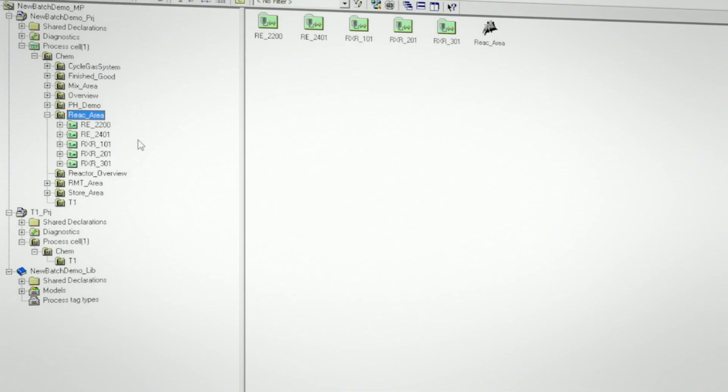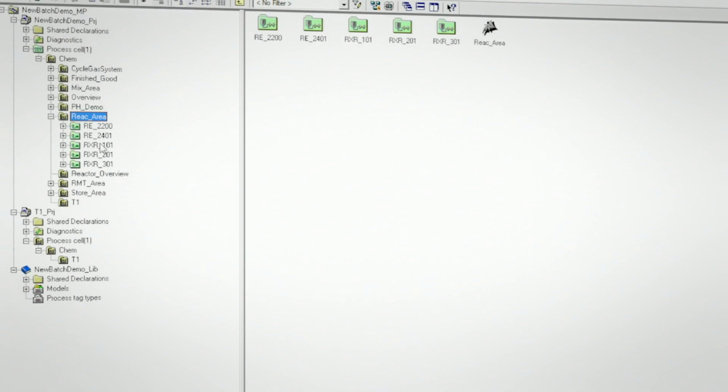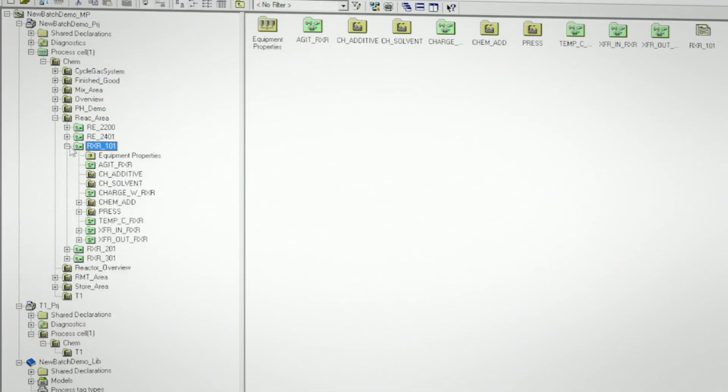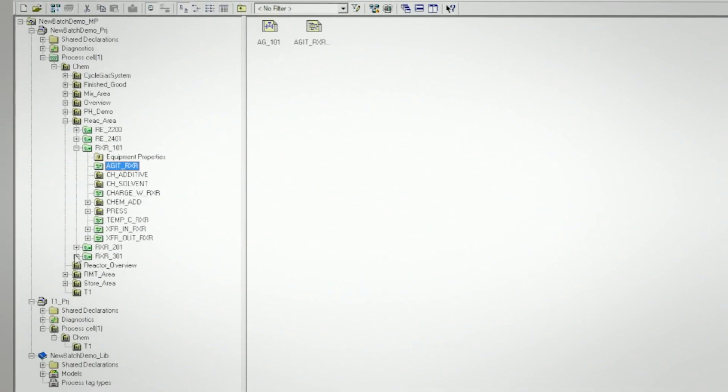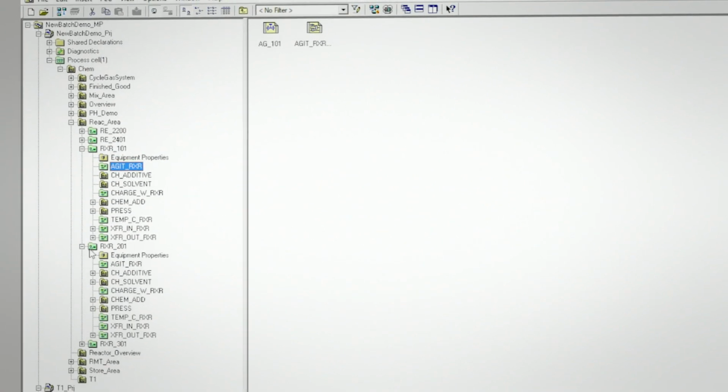The standard essentially describes a method on how to structure batch processes. It defines models and terminology that make the design and operation of batch plants easier and more uniform. S88 is more than just a standard for software, equipment, or procedures. It's a design philosophy. SIMATIC Batch is fully integrated into PCS7. The plant model is configured directly in the plant view of PCS7, organized into units, equipment modules, and control modules.